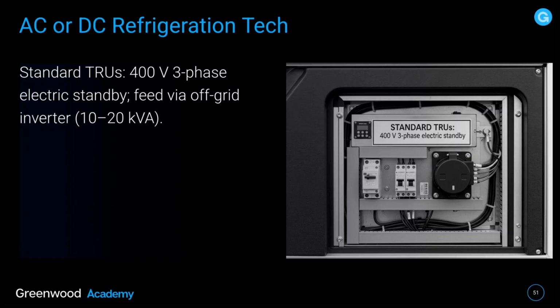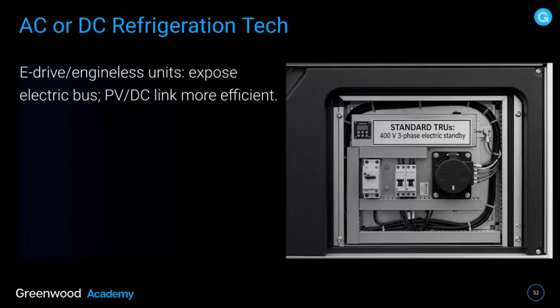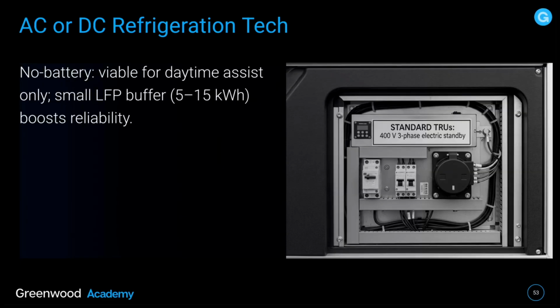Now, let's look at AC or DC refrigeration tech. A standard TRU is 400 volts, 3-phase, electric standby, fed via off-grid inverter, 10 to 20 kVA. E-drive, engineless units, exposed electric bus, PV, DC link, more efficient. No battery, viable for daytime assist only. But if you put in a small LFP buffer, 5 to 15 kilowatt hours, this can actually boost reliability.